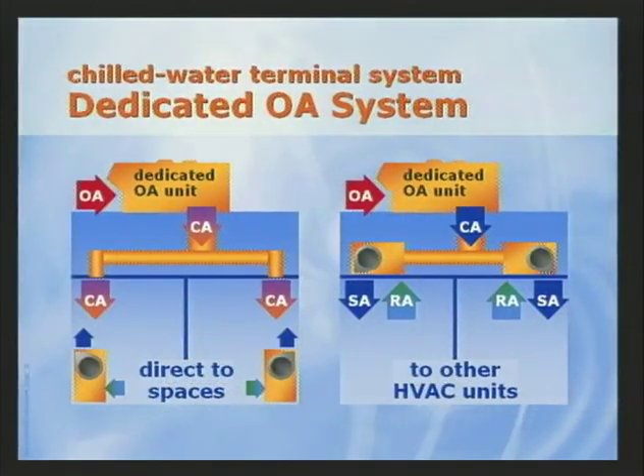Now realize that the temperature of the air leaving this heating coil typically ranges from 55 to 75 degrees. So the water used for tempering does not need to be very hot. Many standard water-cooled chillers can provide suitable temperatures just by operating at a slightly elevated refrigerant condensing temperature. Now, the last dehumidification enhancement we'll discuss for chilled water terminals is to use a dedicated outdoor air system. As its name implies, this system devotes one air handler to cooling and dehumidifying all the incoming outdoor air used for ventilation. Then this dry outdoor air is delivered directly to the spaces or to the individual terminal units. Meanwhile, units located in or near each classroom condition recirculated air to offset the space sensible loads.